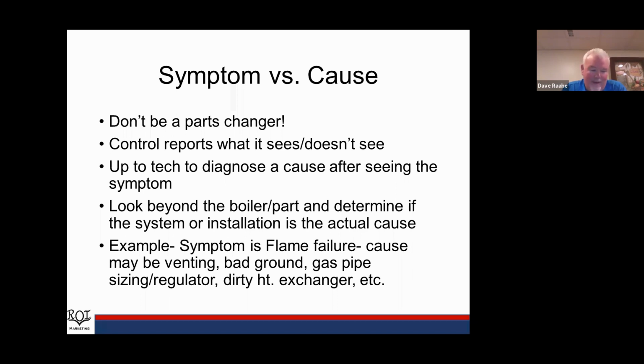If you look in the manual, one of the things they'll tell you is to check your flame rod. For you guys, I don't know if you've seen a flame rod before. I'm going to hold it up to my camera, once I figure out where it's at here. It's nothing more than a piece of metal rod that goes through a ceramic insulator, and that reads flame current back through. I want to say we probably sell hundreds, if not thousands of these in a year's time. I've maybe seen 2 bad ones. But what can happen to these due to bad venting, bad grounding, a boiler that's not set up right, is they may bend out of shape. They may get coated with a coating that limits their ability to transmit flame current.